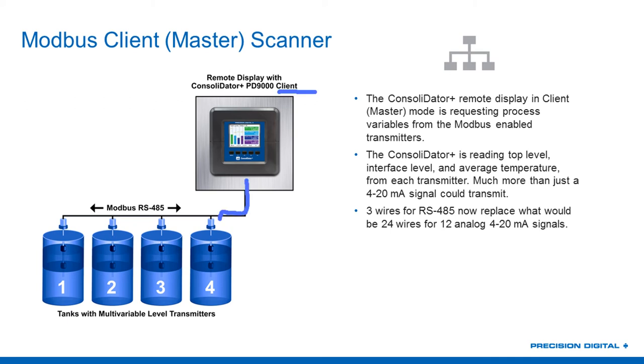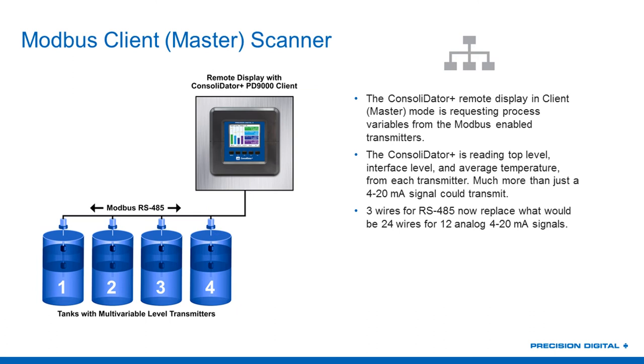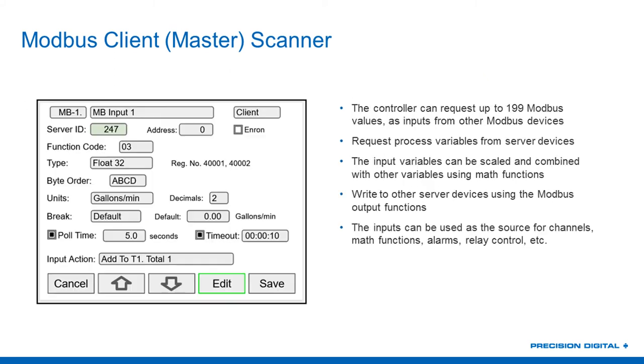The Consolidator pulls data from each transmitter and gets a response back, then treats it like any other process variable — any other 4-to-20 milliamp value. You can mix your inputs into the Consolidator, and once they're in there as inputs, you can base your 4-to-20 milliamp outputs on them, have them trigger relays, and do all the sorts of things you would do with values brought in via a traditional 4-to-20 milliamp line.